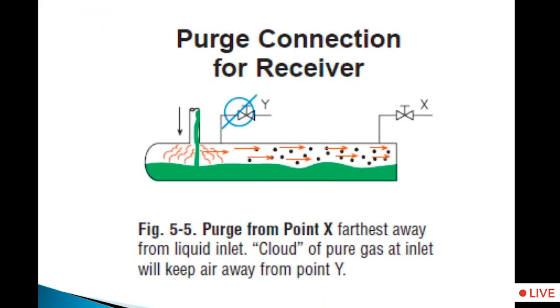The next item, as I show you, is the purge connection for the receiver. As I mentioned, keep it away as much as possible, because the inlet has a cloud of pure gas, and if the gas purge connection is too near to the liquid inlet, it may waste your ammonia gas. So keep it as far away as possible.